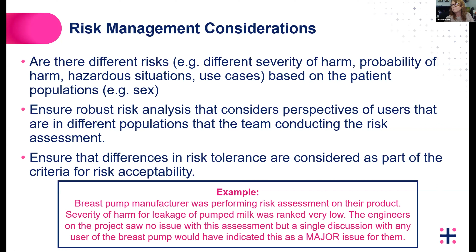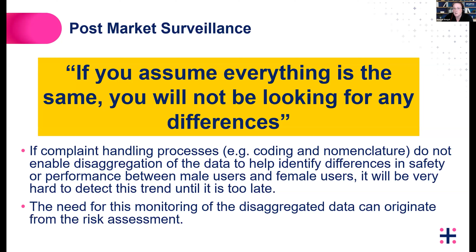Okay, post-market surveillance. If you assume everything is the same, you will not be looking for any differences. So I think complaint handling processes need to allow for the disaggregation of data to help identify differences in populations, between male users and female users. If this is not possible, you're not going to be able to detect trends between your different user populations. And again, this can feed out of the risk assessment. If you've done your risk assessment in a way that accounts for the different populations using your device, or that your device is intended for, then that will tell you if you need to be disaggregating your data in the PMS stage. But if you treat your device as sex neutral the entire way through the process, then you're not going to be able to see specific trends based on user.